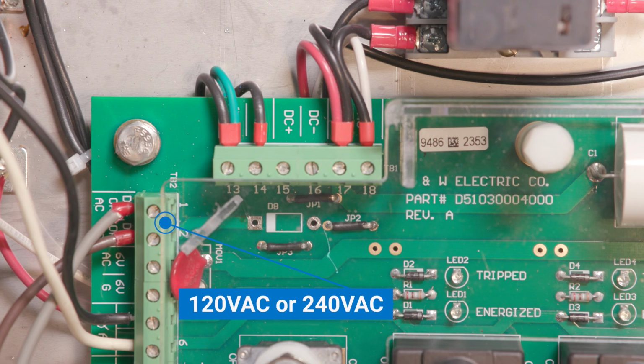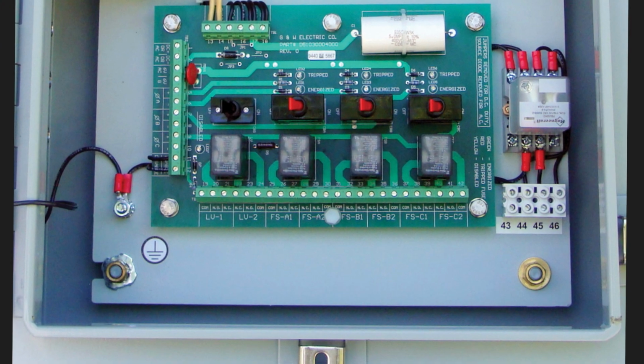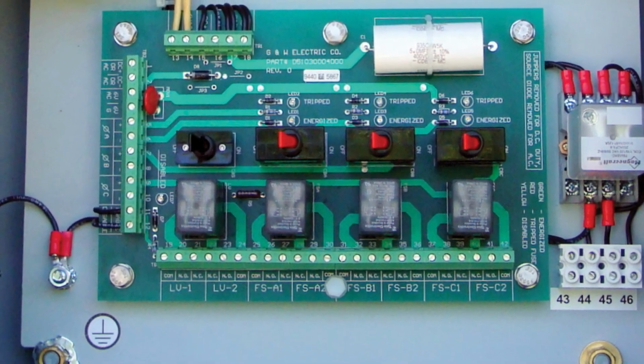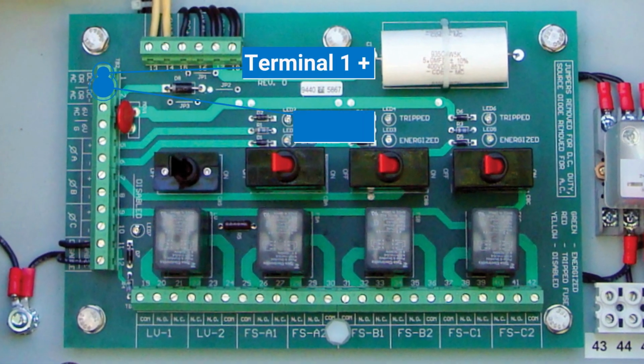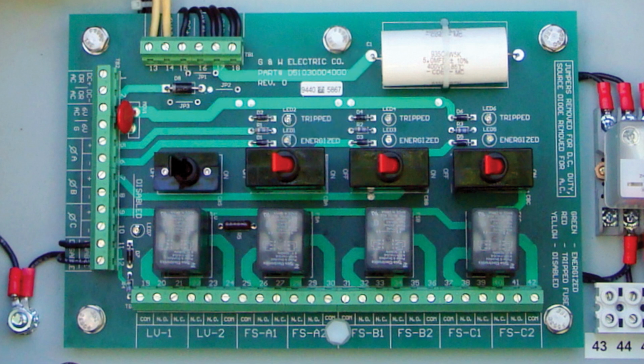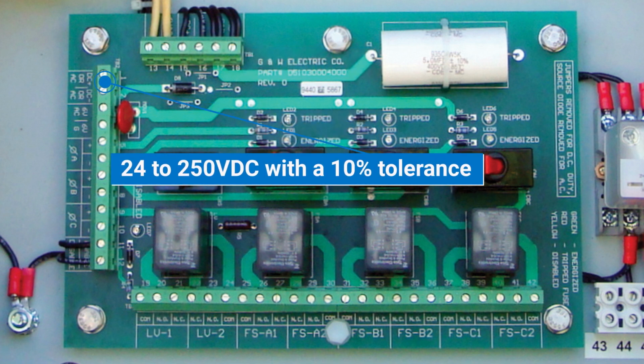and 2. For situations with a DC power supply configuration, before energizing the control power, verify that the DC polarity to terminal 1 is positive and terminal 2 is negative. Voltage at terminals 1 and 2 will be the supplied DC voltage, 24 to 250 VDC, with a 10% tolerance.